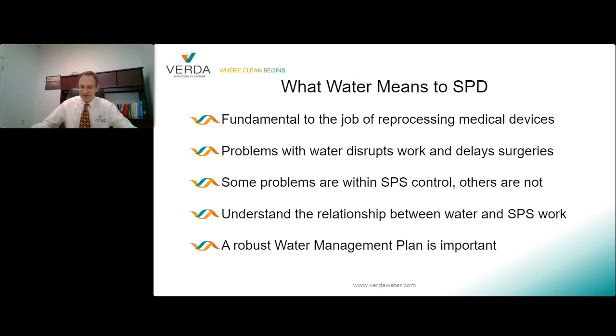Every SPS should have a water quality assurance plan. First, what is the validation and verification plan for a new system? Second, what parameters are going to be monitored? Third, where are they going to be monitored, and where are the sampling ports? Fourth, what ranges or levels will trigger an action? Fifth, what's the protocol when an actionable event happens? And sixth, is there a mechanism for documenting the root causes of the issue and how this will be prevented in the future? All of this should go into your plan.